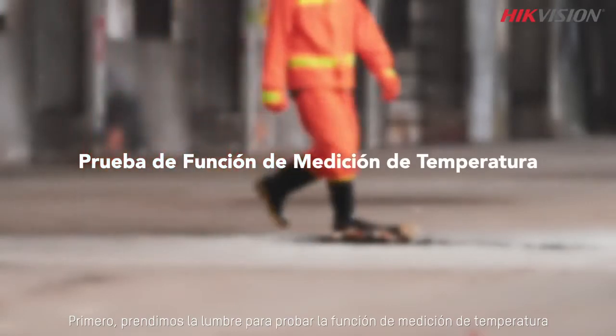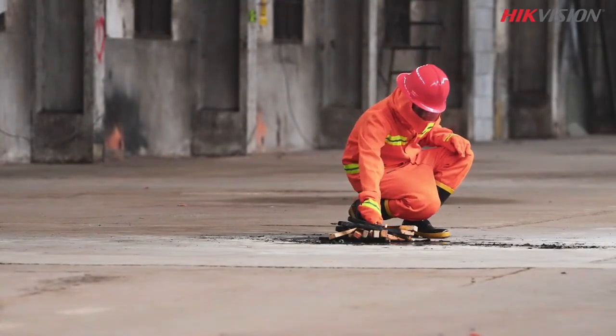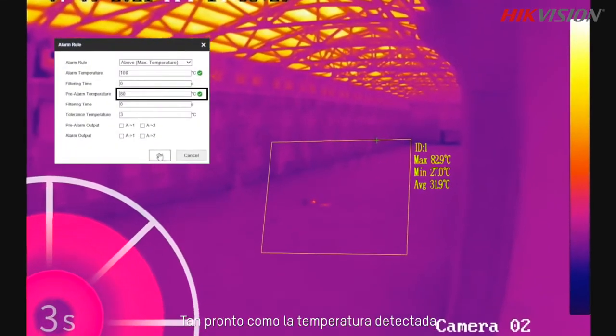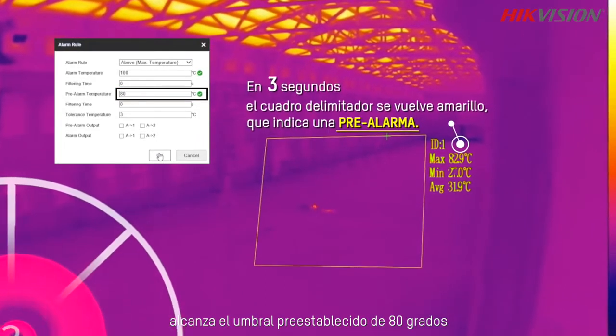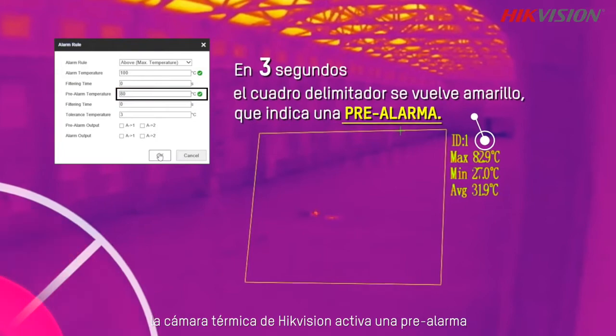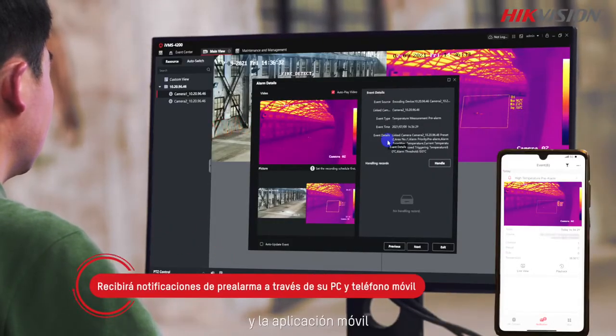First, we set up a fire to test the temperature measurement function. As soon as the detected temperature reaches the preset 80-degree threshold, a pre-alarm is triggered by Hikvision's thermal camera. A real-time image of the spot is pushed to the PC client and the mobile app.